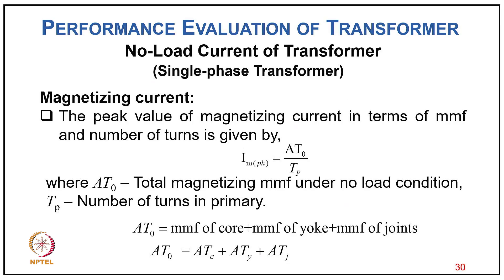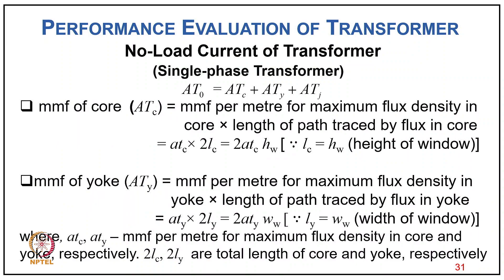If all joints are assumed equivalent to an air gap of length lg, the total ampere-turns for the transformer magnetic circuit is AT = ATiron + 800,000 × lg × Bm. The magnetizing current is Im = (AT_iron + 800,000 × lg × Bm) / (√2 × T1). The total MMF AT₀ = ATc + ATy + ATj (core + yoke + joint contributions).